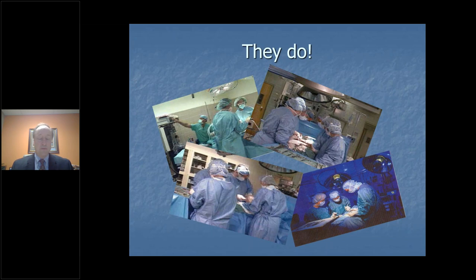And it gets very uncomfortable in there. So oftentimes it's the surgeon that asks for the temperatures to be dropped lower and lower, and when you do that, you really need to have an understanding of the humidity level that's in the room, and we'll talk a little bit about that. It's not just for the doctor's comfort and the patient's comfort, but it is also for the health of the patient. Sometimes you've got to lower the body temperatures. Sometimes you don't want to lower the body temperatures if it's small, you know, adolescents or pediatrics. So there are a number of things within the healthcare environment that we really need to understand the dynamics of the temperature and the humidity control.